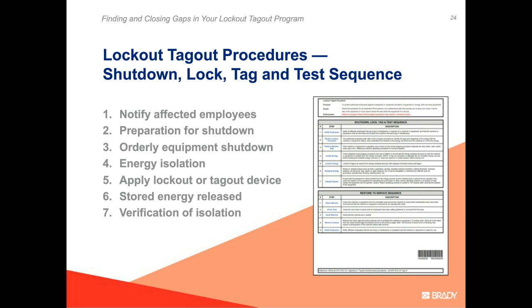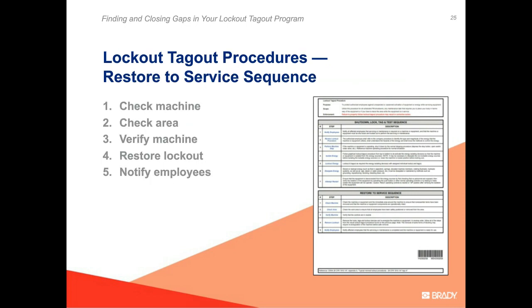The restore-to sequence comes below our shutdown, lock, tag, and test sequence, and it's basically the opposite of the shutdown sequence. You check the area and the machine to make sure it can actually be started back up and that maintenance has been completed. Once verified that the machine is fully ready, you restore the lockout, remove all your locks, and notify employees that the work has been done.